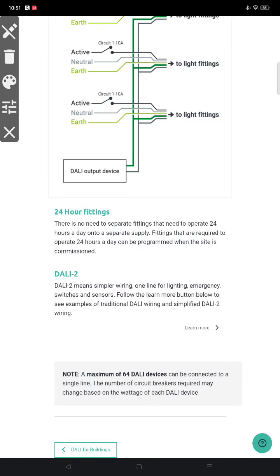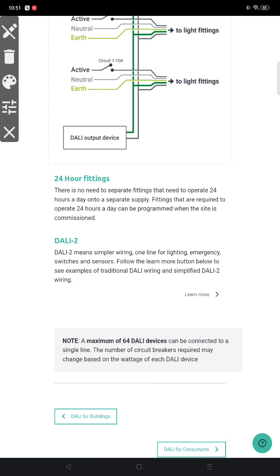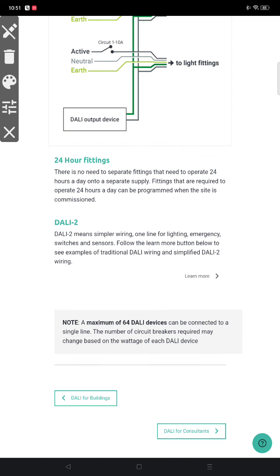24-hour fittings: there is no need to separate fittings that need to operate 24 hours a day onto a separate supply. Fittings that are required to operate 24 hours a day can be programmed when the site is commissioned. So DALI 2 means simple wiring, one line for lighting, emergency, switches and sensors.